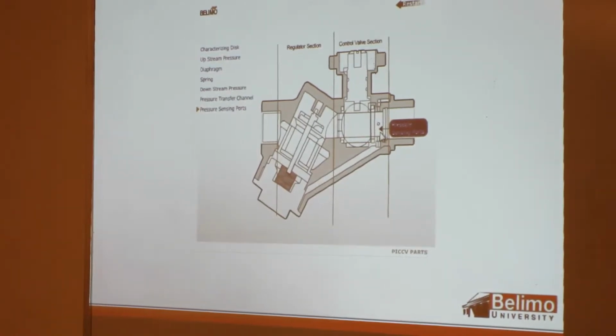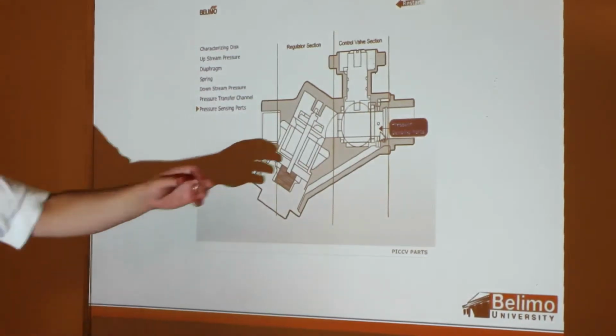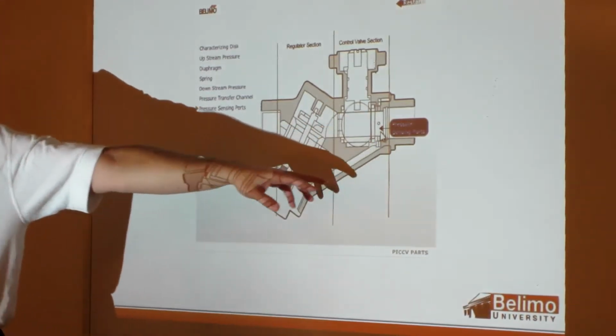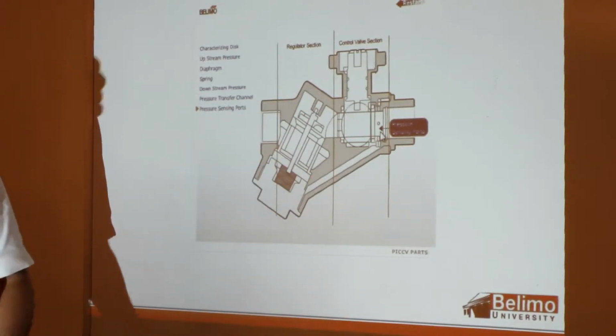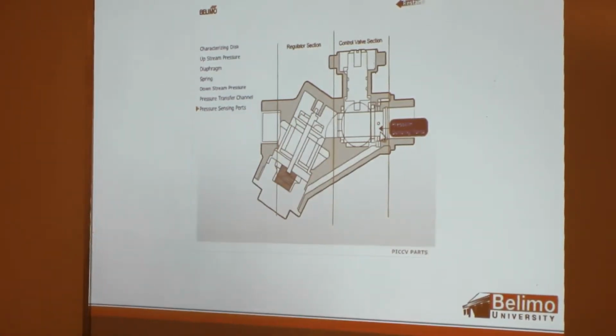Now, around the opening at the end of the valve are the pressure sensing ports. One thing that those of us that were with Belimo at the time this was introduced were concerned about was, well, those look like some pretty small holes around there. Couldn't those get clogged? They don't. The reason being is you've got flow flowing by there, and so it's a Venturi effect. You know, if the flow were to stop, yeah, maybe something could stop over one of those holes. As soon as water starts flowing again, it pulls everything with it. So there's no problem there.